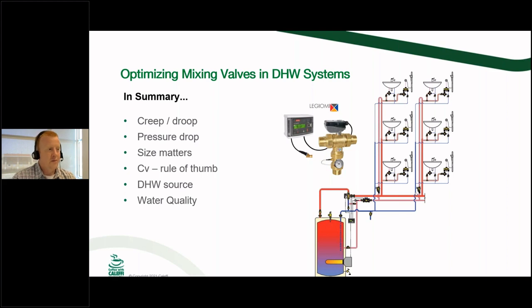Obviously, big single speed circulators with manual balancing valves that were never set up properly are going to be the worst case scenario. But you look at thermal balancing valves that are set based on a temperature, not a fixed flow rate, in conjunction with that variable speed circulator. I think that's going to be your best case scenario. Obviously, you're going to pay a little bit more upfront for that kind of setup, but you're going to have a lot easier time setting those balancing valves, and that customer is going to enjoy the energy savings for the life of that building, or at least the life of the circulator.